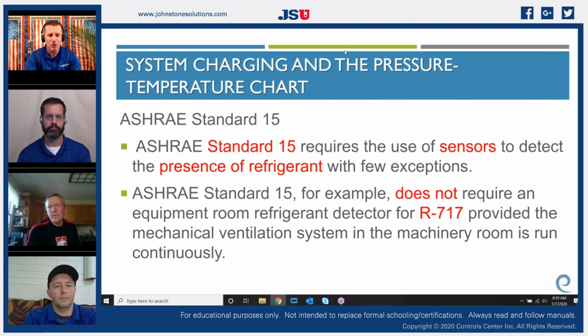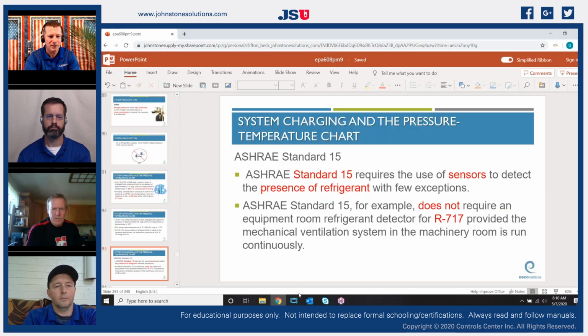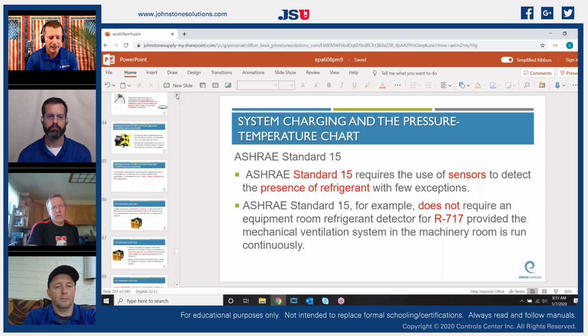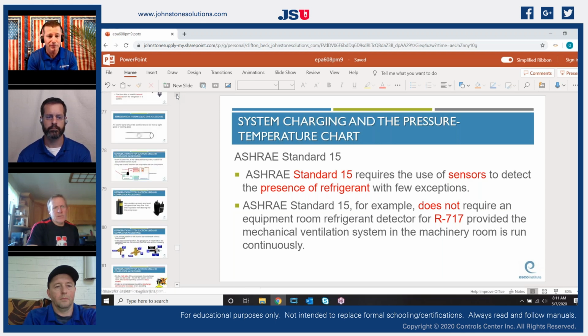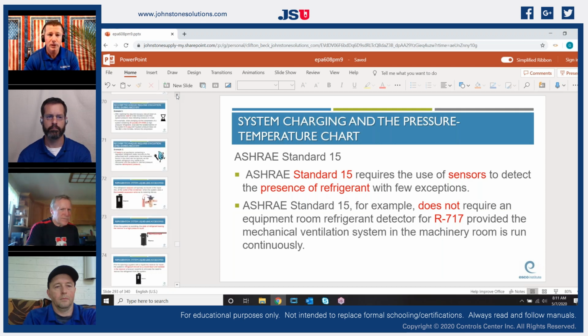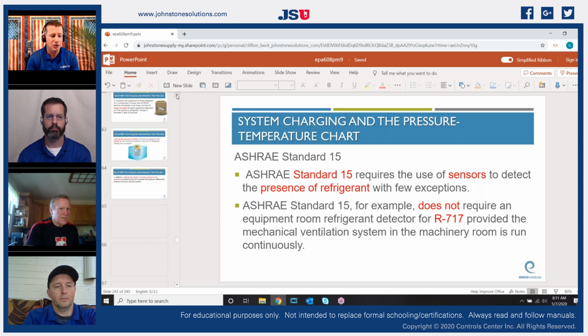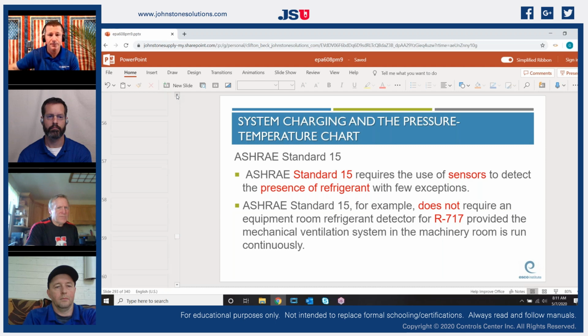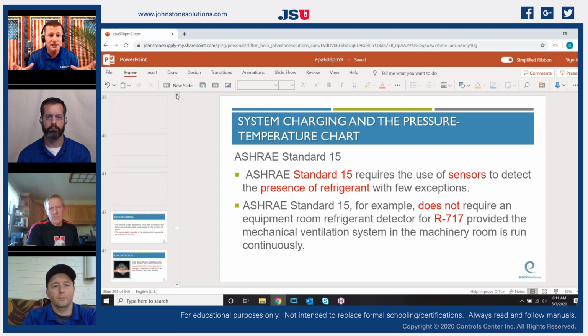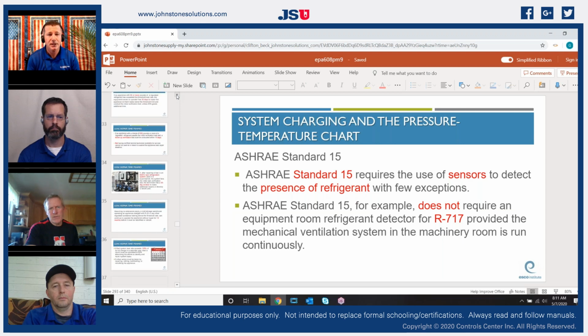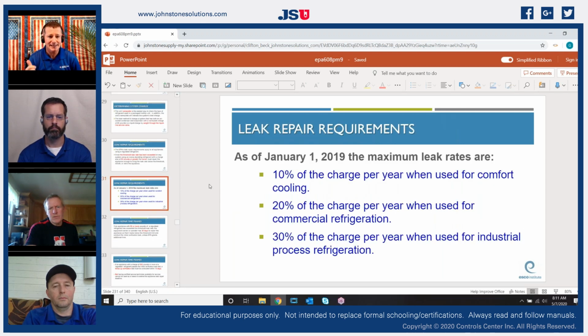And one of the things you want to go back to too, Greg, if you can pull it up, if not, we can just talk about it, is understanding what those leak rates are. So when we're talking about type 2, we're talking primarily comfort cooling. A comfort cooling system can be an air conditioning or heat pump system in a residential that has just a few pounds of refrigerant. It could be a 20 or 30 or 40 or 60 ton packaged air conditioner, or it could be that 250 ton chiller that is sitting outside or in a mechanical room that is providing refrigerant for a whole bunch of different indoor heads. It could be a VRV system that has a single condensing unit and has multiple indoor units. And so how much refrigerant is in that system and what your application is going to dictate what that leak rate is.